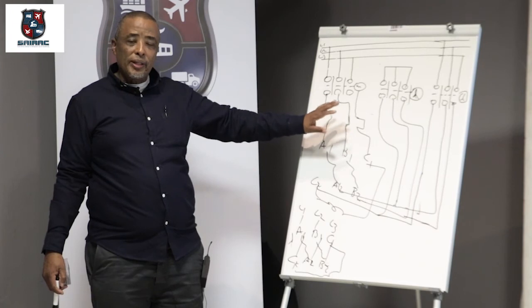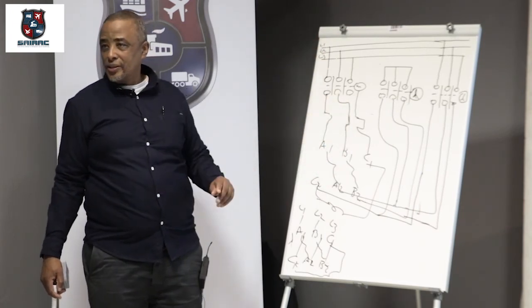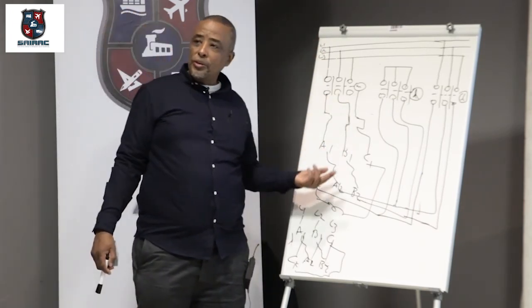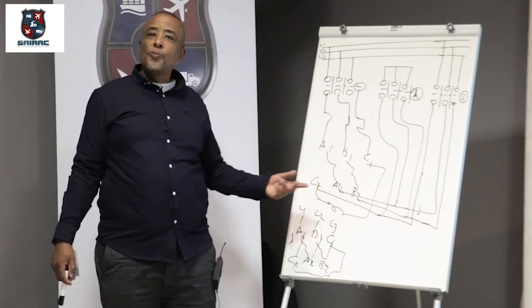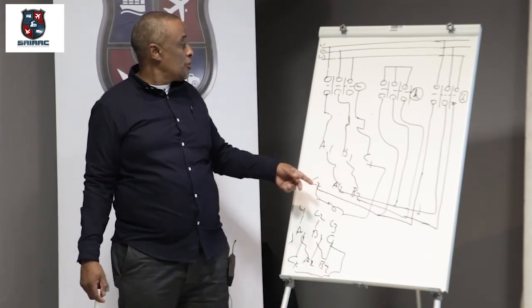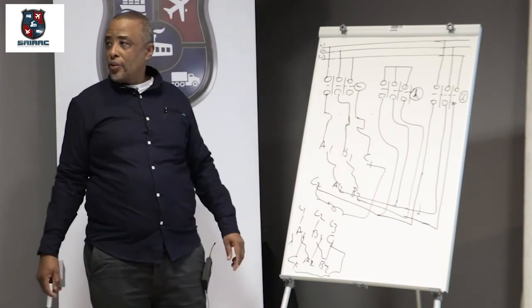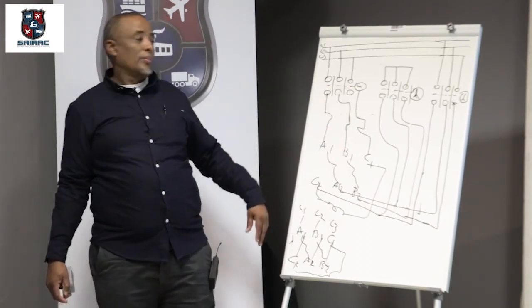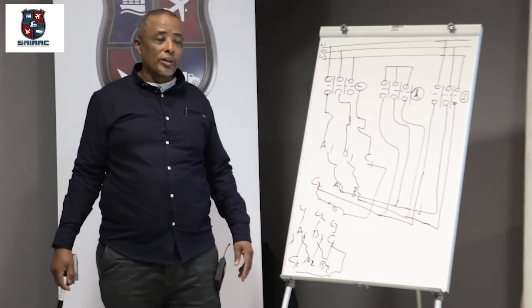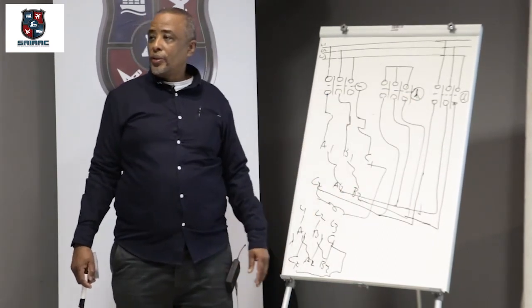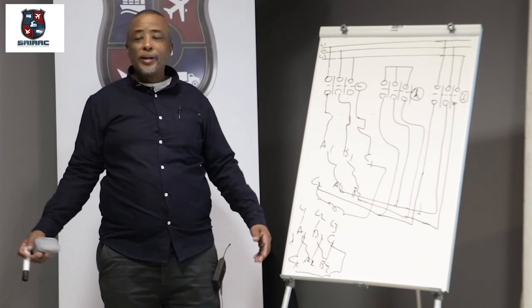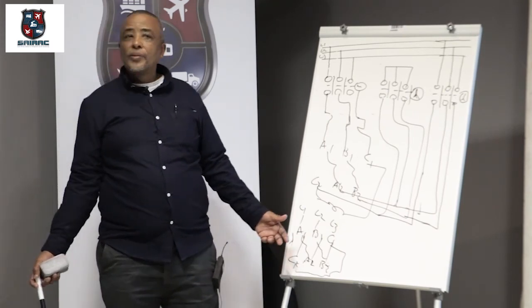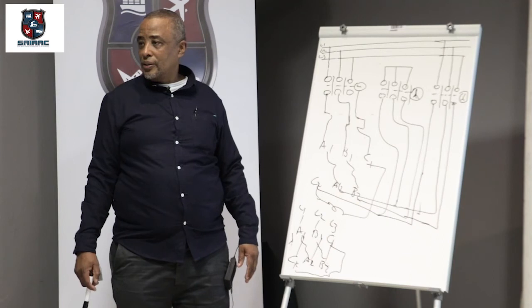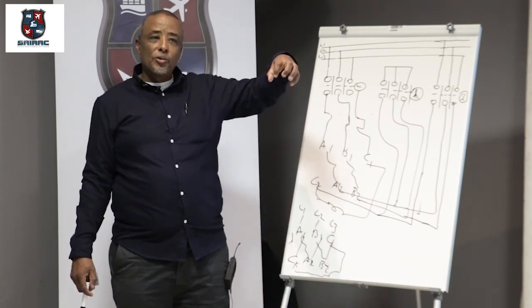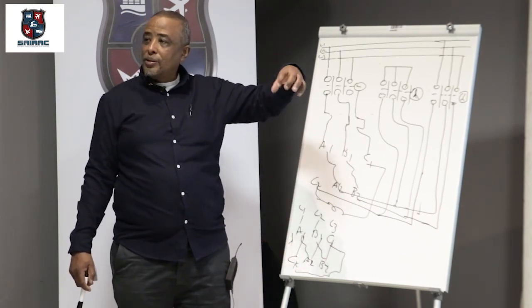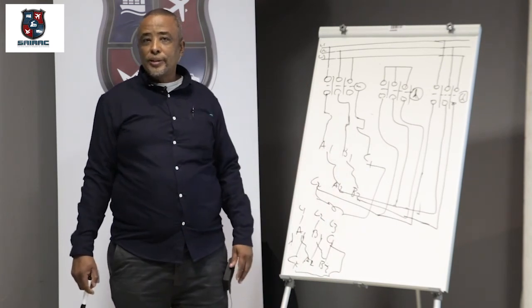Your control circuit, again, you could use PLCs. Stop and start on your input. Your outputs, one output will go to your main contactor coil, other one to your delta contactor coil, other one to your star contactor coil, and then your timer could either be, if it's an electrical timer, then you need to go to a timer coil as well. If it's a mechanical timer, it just fits normally as an auxiliary on top of the contactor.